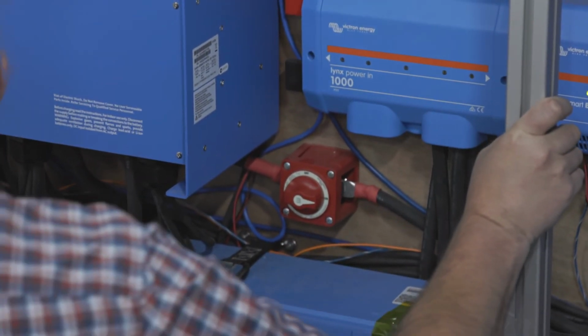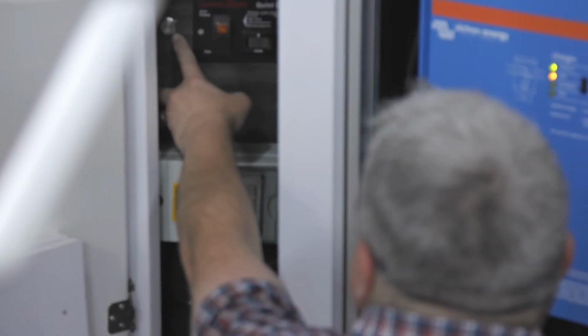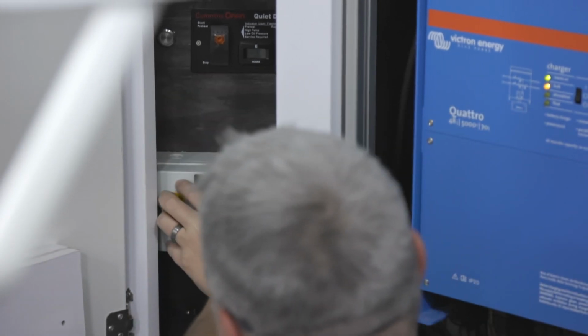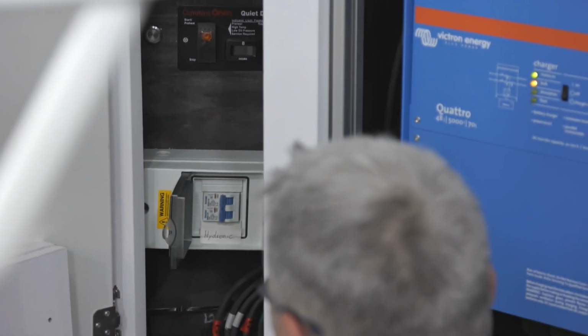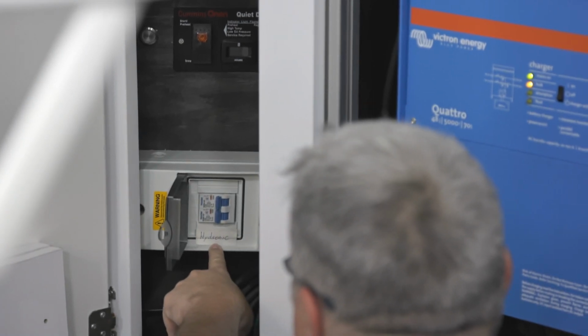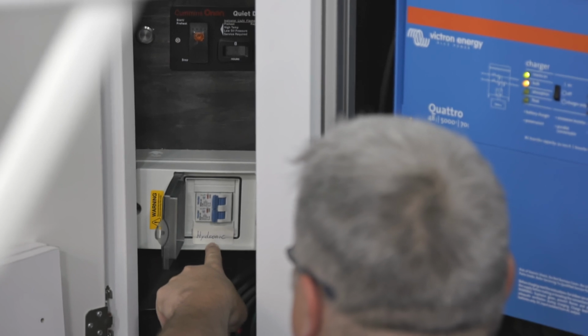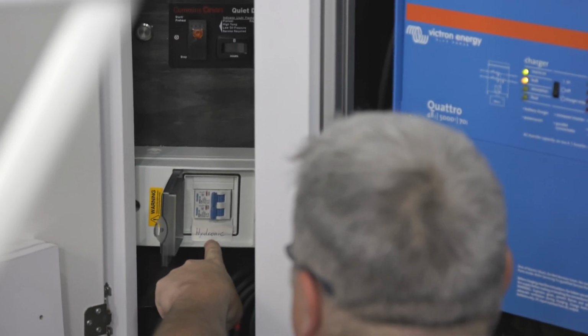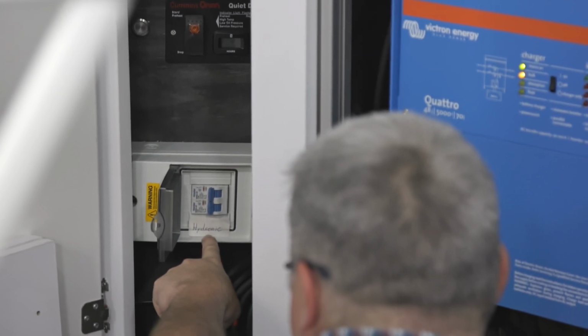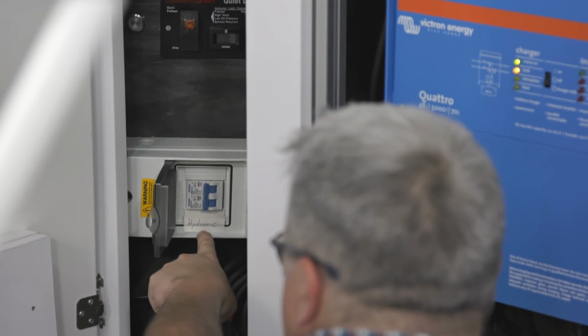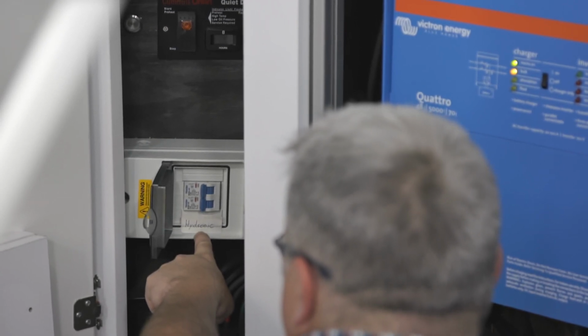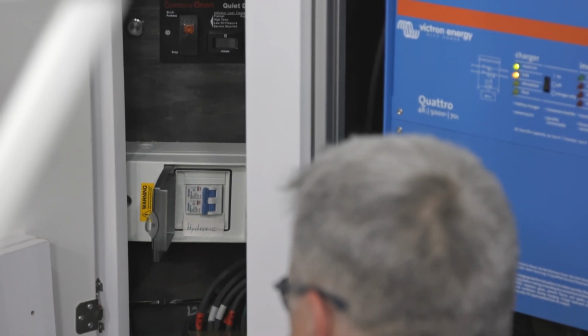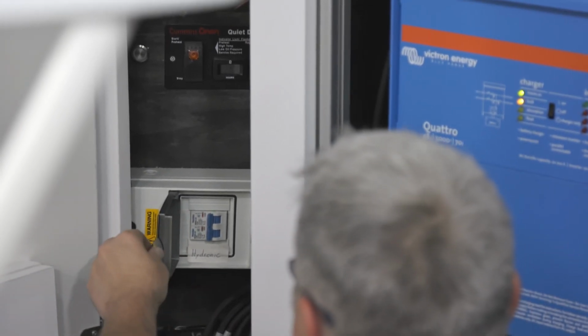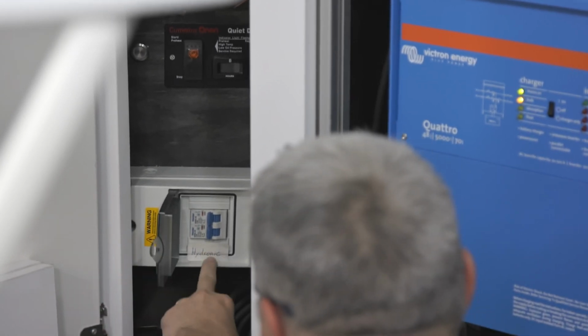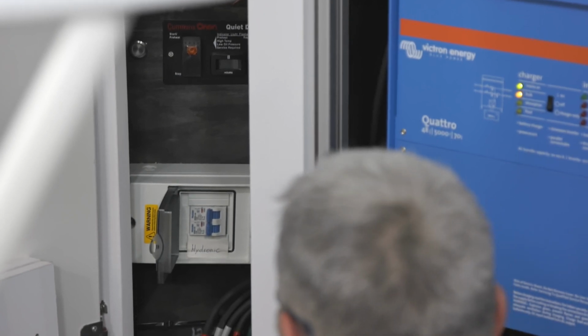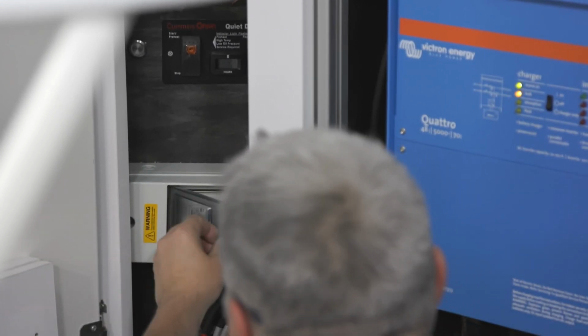Let's see. Over here, I've already mentioned that this is the main system switch, and below it is a set of circuit breakers. On this bus it's labeled hydronic, and those are the electric heating elements in the hydronic system. We really should only be using them if for some reason the diesel furnace back there has failed. This is a redundant means to provide hot water for the sinks and for heating. I think you ought to start the generator if you think you need to turn these on, because they will consume a lot of power and drain the batteries fairly quickly. So by default, I would leave them off.